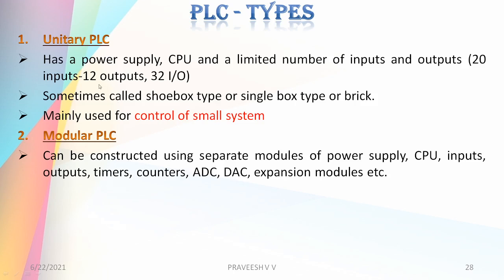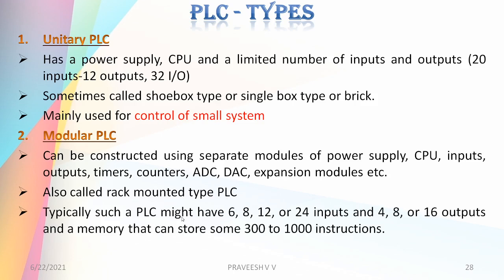In the unitary PLC, everything is fixed and there are not many additional components or modules available. Modular PLCs are also called rack-mounted type PLCs — you can add or remove modules from the rack. Typically such PLCs might have 6, 8, 12, or 24 inputs and normally 4, 8, or 16 outputs, and a memory that can store around 300 to 1000 instructions and more.